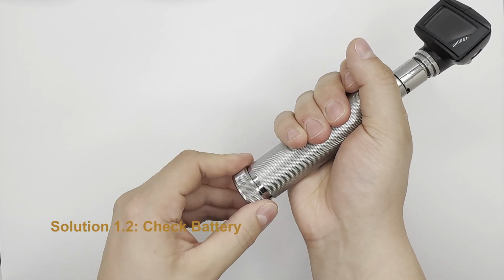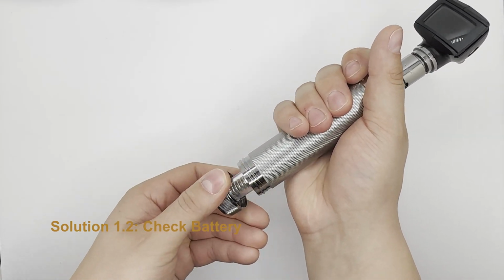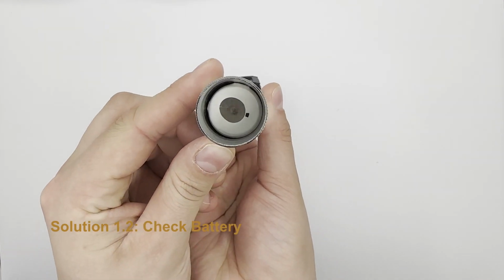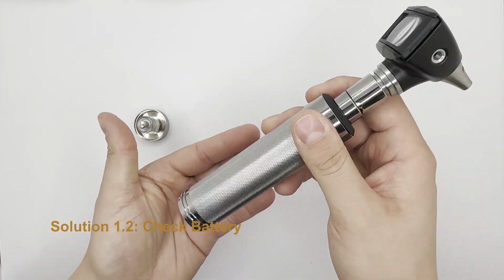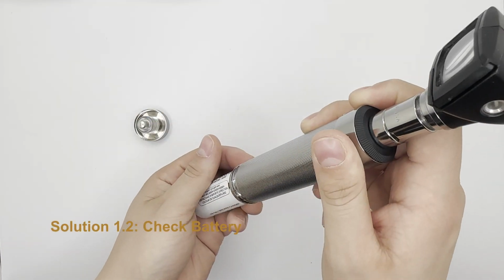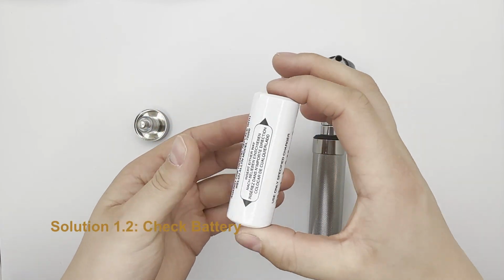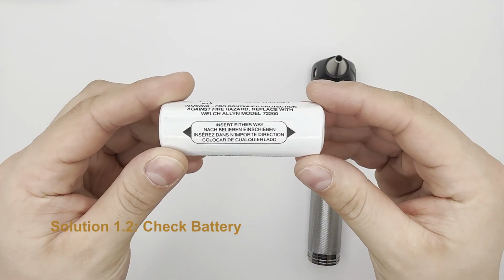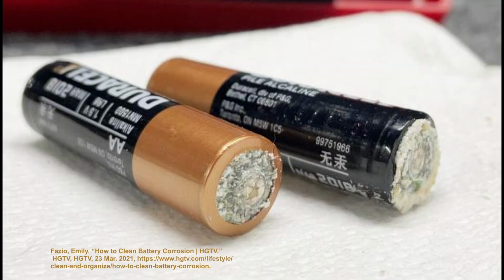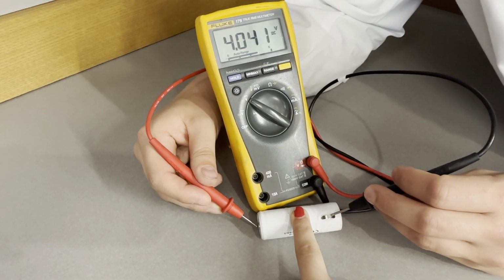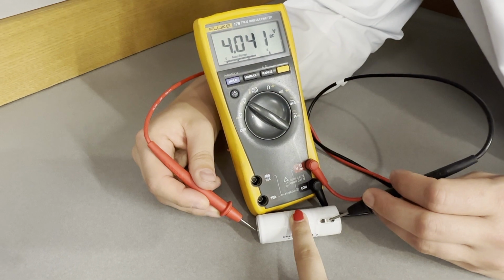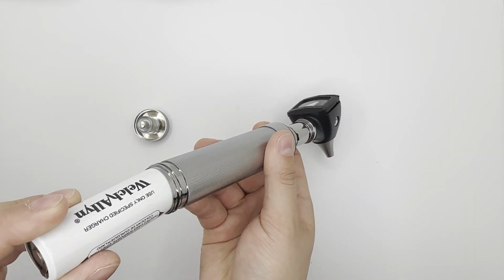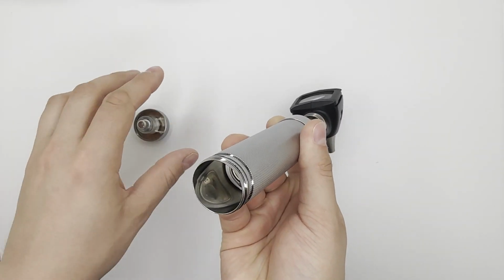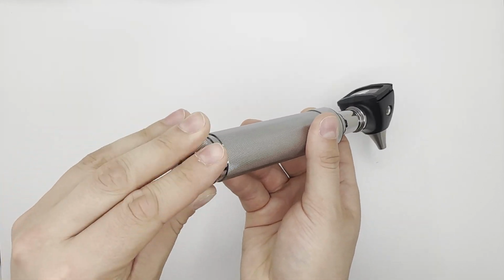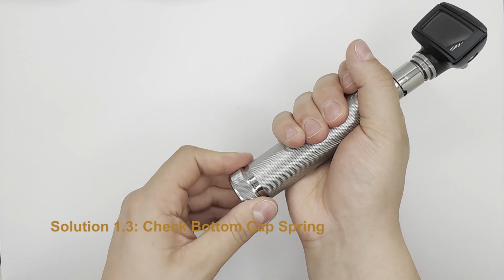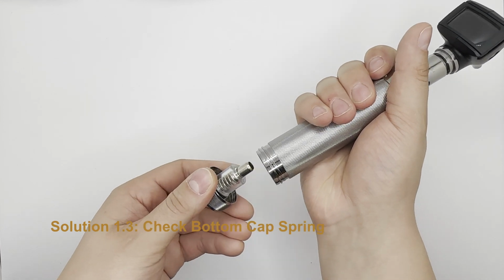If charging the battery doesn't work, it's possible that it can no longer hold a charge or is damaged. Remove the battery from the handle. This involves unscrewing the cap on the bottom of the handle and firmly tapping the shaft of the handle on the palm of your other hand until the battery shakes free. Check for signs of visible corrosion. Use a multimeter to test that the battery still carries a voltage difference. If the battery is damaged or can no longer hold a charge, a new battery may need to be purchased. With the bottom cap removed, check that the bottom cap spring is present.